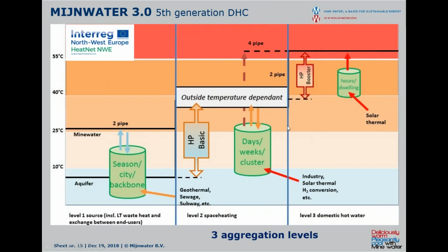This is a picture which is more or less showing the idea of what we do. In fact, we have 3 aggregation levels. So we have the city level where we have a source which might be somewhere between 10 and plus 25 degrees in our case. And we have a buffer connected to this level to equalize in time the energy demands and energy deliveries. We can do this on mine water, then we are really high temperature already, but we also can do this on an aquifer, and then we might take this energy from 10 degrees Celsius. There is a heat pump going from this level of heat to an area of temperature which is outside temperature dependent. So we bring it up from maybe 25 degrees to 45 degrees, which is done within the district or within the complex of buildings.